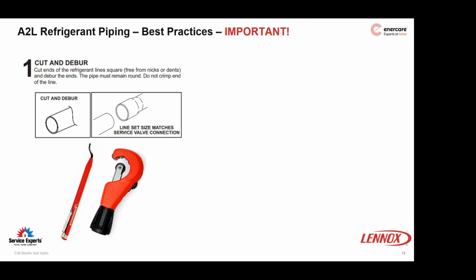Now, a nice side note for those of you in the field, and some of you may already know this because you're using or testing them: there have been some tests on no-braze fittings. They're a two-wrench style, almost like a compression fitting, that collapses around the piping and creates a seal. We tested them in our lab too. They held without any trouble, as far as I could tell, to 500 psi. I think some final details are still being ironed out, so ideally we'll get to the point where we may not even have to use torches. We're using a double wrench compression style fitting.